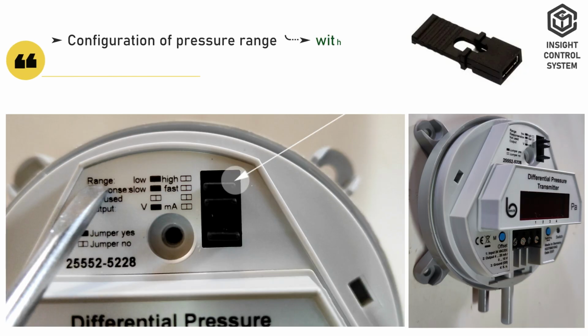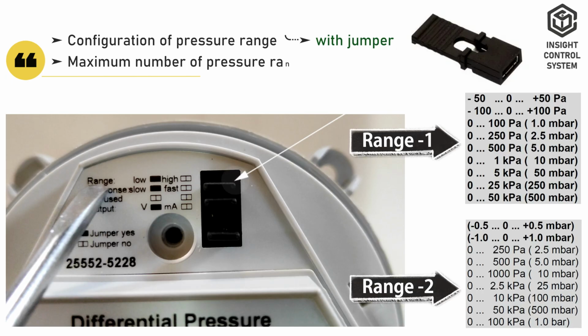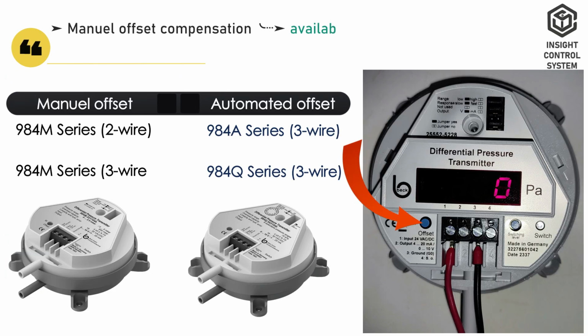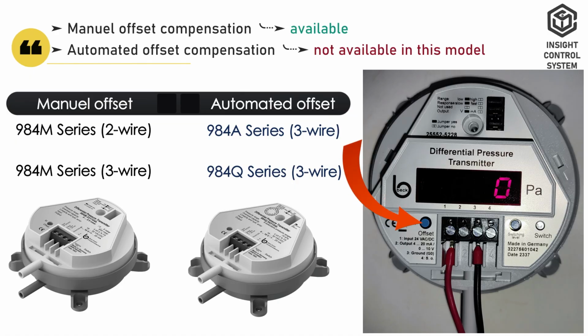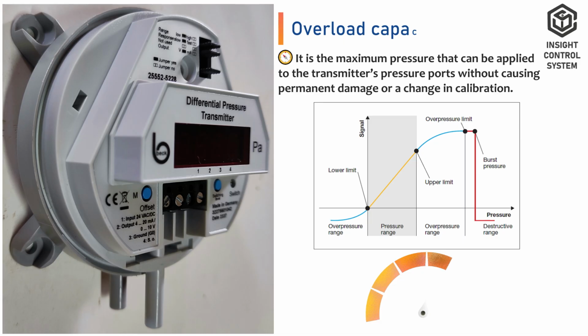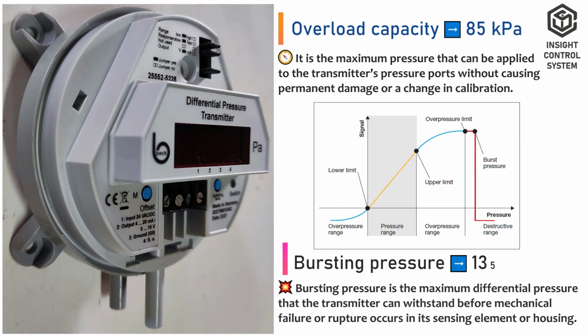Measuring data: the pressure range is configured via a jumper. The maximum number of pressure ranges is 2. Manual offset compensation is available. Automated offset compensation is not available in this model. Overload capacity is 85 kilopascals. Bursting pressure is 135 kilopascals.